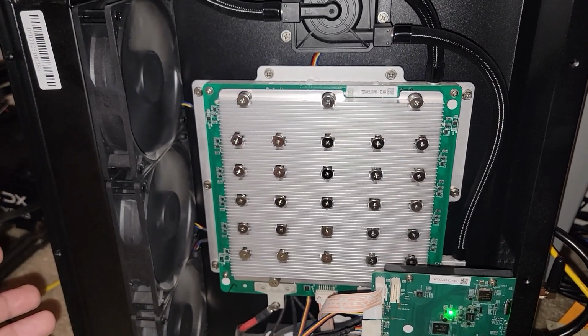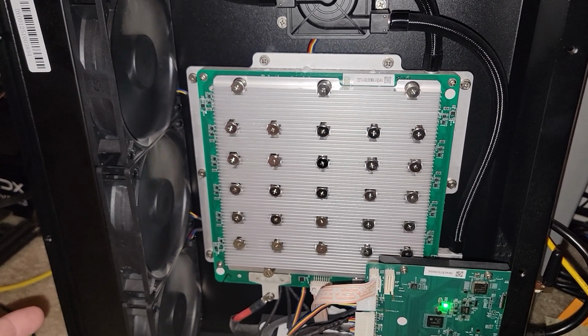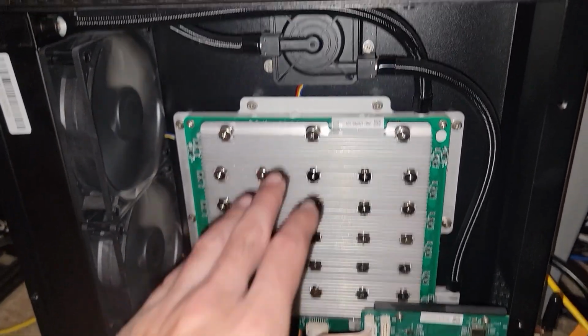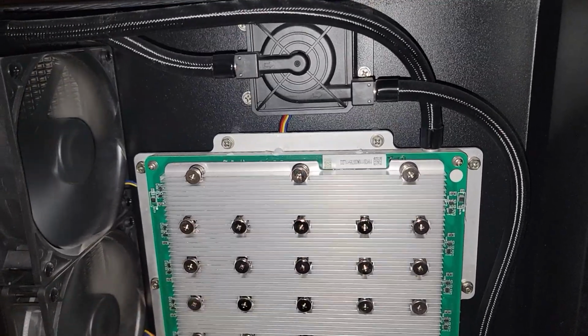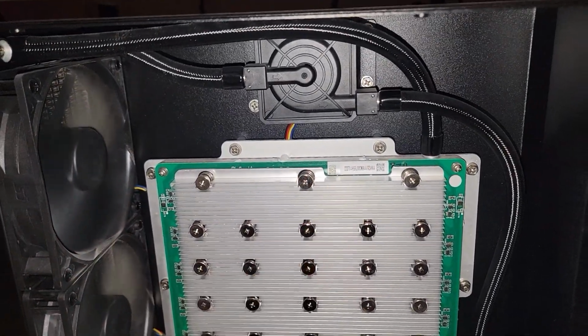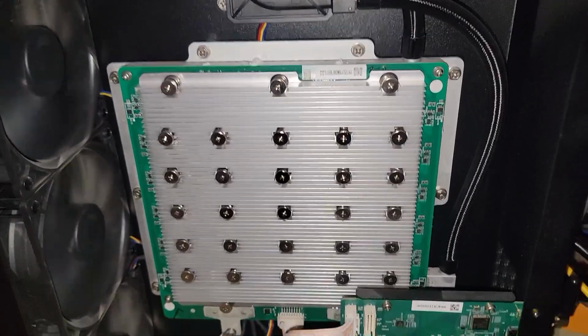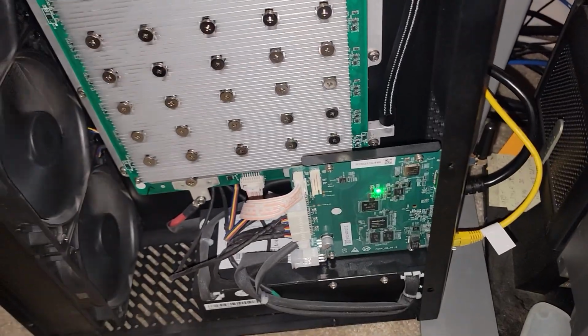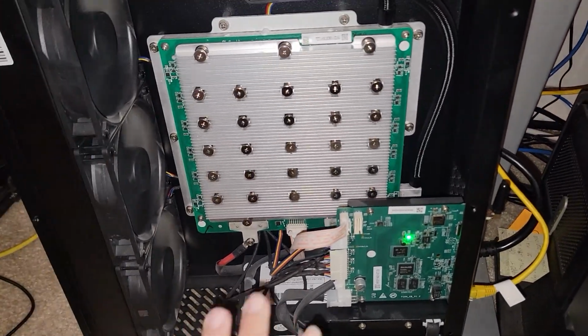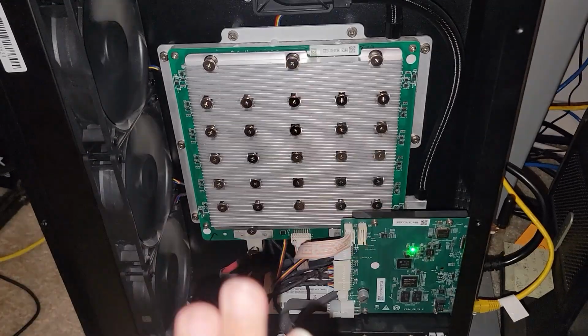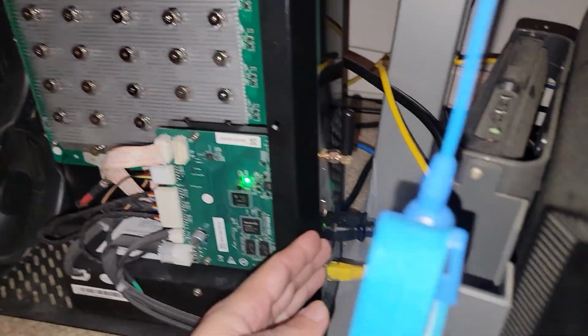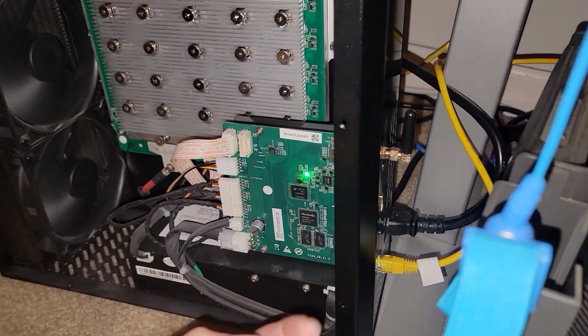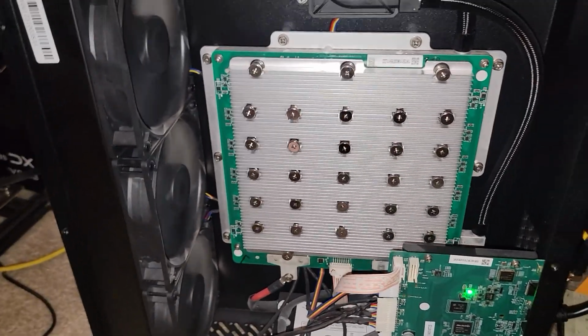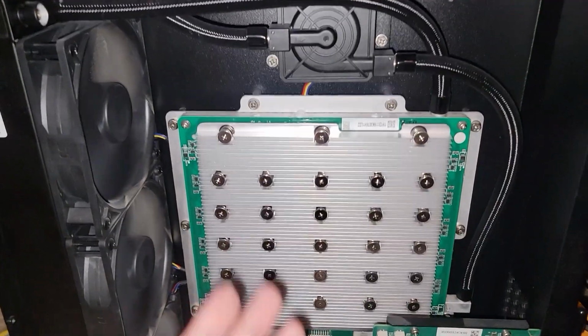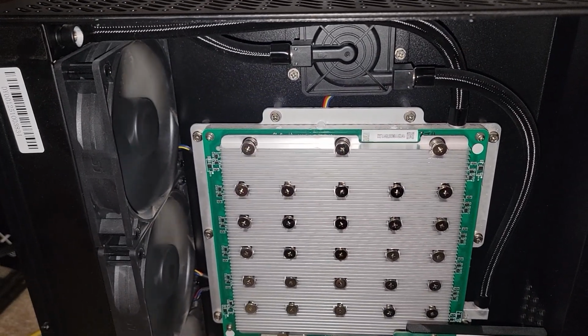I heard one of our viewers was talking about a clicking noise, and I don't think the pump would be making a clicking noise, but it's possible if maybe there were too much air bubbles going into it, it wasn't laid down properly. On the back of the machine there's a sticker that tells you it can only either stand up the way it is or lay down where this board is facing downward, or the front IO is facing upwards towards the ceiling. If you lay it down the wrong way, you could cause issues, cavitation in the pump, maybe cause some damage.